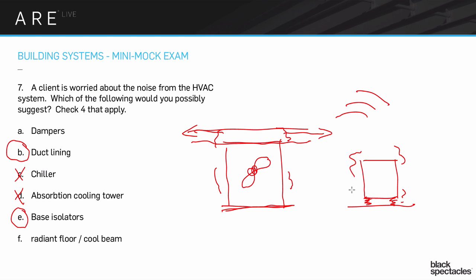The other way to do that is often you'll see like big duct work elements that are attached to air handling units. So the fans are shaking the duct work, and so these things are hung with wires, and so the wires make it very difficult for the duct to send that vibration up to the structure.